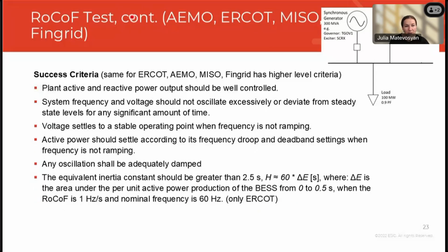What's expected here is that plant active and reactive output should be well controlled. System frequency and voltage should not oscillate excessively or deviate from steady state levels. Voltage settles at a stable operating point when frequency is not ramping anymore. Active power should settle according to frequency droop and deadband settings when frequency is not ramping, and any oscillations shall be adequately damped. ERCOT requirements again define equivalent inertia constant and explain how it is calculated in the test event.